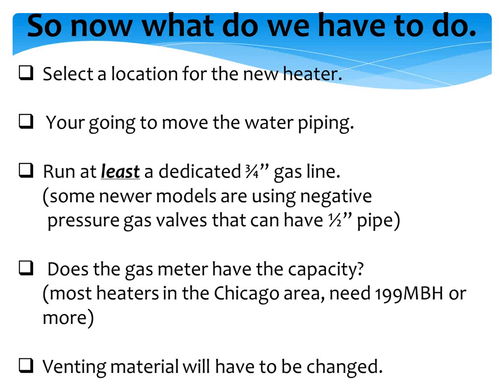You're going to have to run at least, and the reason I say least, a dedicated 3/4 inch gas line. Some of these newer models that are coming out are using negative pressure gas valves so they can get by with a 1/2 inch. But the reason I say least is it's just like with any other gas appliance, the length of the run from the meter to the appliance is going to determine what you're going to have, but you're going to have at least a 3/4 inch. No more 3/4 inch line coming over, dropping down, 1/2 inch going to the water heater, 1/2 inch going to the furnace. We're talking about a dedicated 3/4 inch gas line just for the water heater.